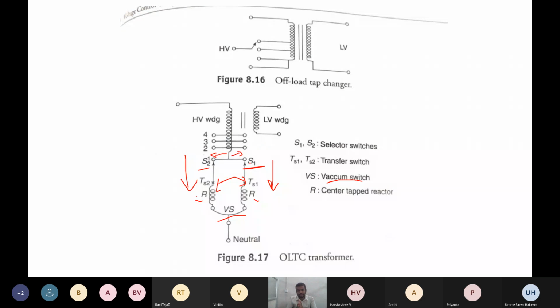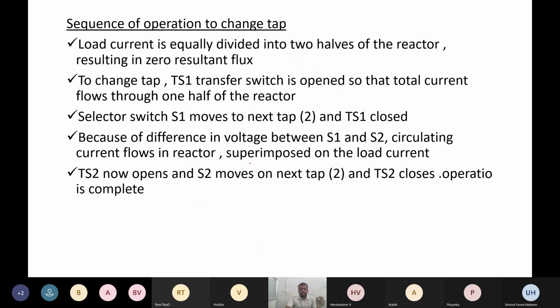The current that is flowing through the load winding should be equally halved through the reactors. So this results in zero resultant flux. So equally divided, it should be balanced. So if you are going to balance the current, at that time the resultant flux will be zero. So this is the first step. Next step, to change tap, TS1. So TS1 and TS2 are our transfer switches.